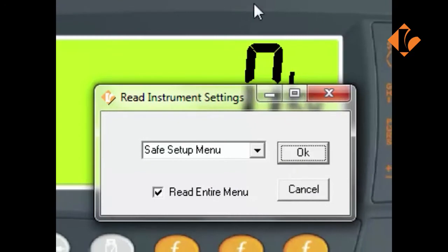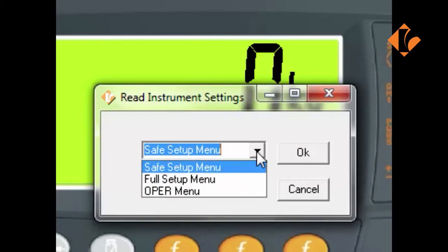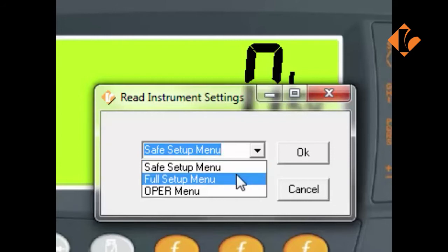Once pressed, there are three levels of access to the settings: Safe Setup Menu, Full Setup Menu and Operator Menu. The Safe Setup Menu allows for changes to be made within the indicator that don't affect the metrology of the indicator. The Full Setup allows for full access to all settings, including the metrology or calibration of the indicator.